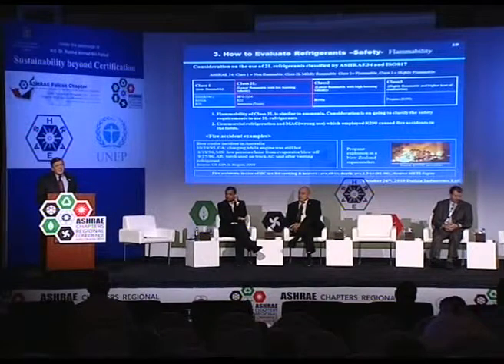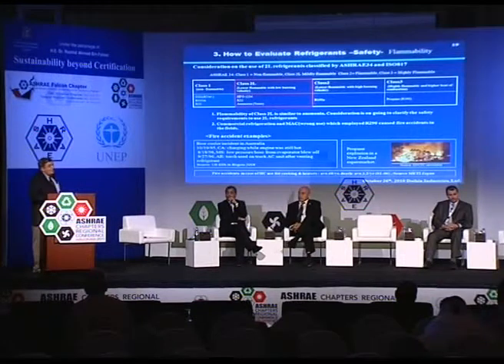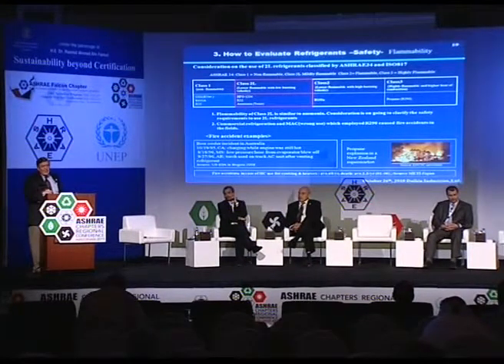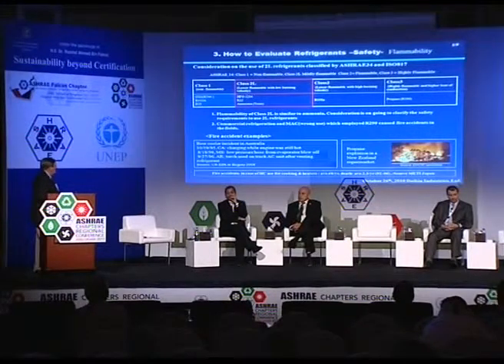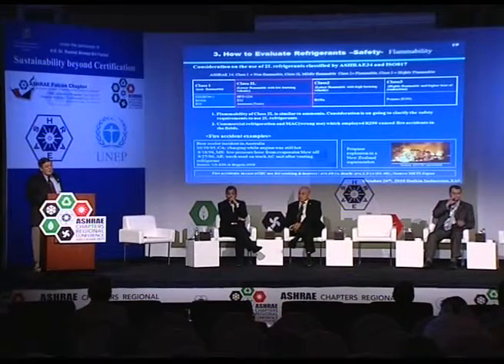The second thing to look at in picking the right refrigerants is the safety classification, and there's a slight issue with new refrigerants that has to be addressed. We're used to dealing with refrigerants classified as A1, basically safe refrigerants. As we move to R32 and the HFOs, they're classified as 2L, slightly flammable. Understanding that and how you design your equipment is critical for customer safety, as compared to Class 3, like propane, which is highly flammable.